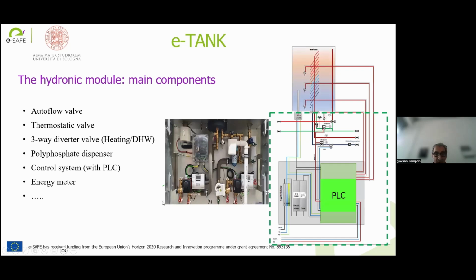The hydronic module's main components are the Autoflow valve and a three-way thermostatic mixing valve for the limitation of temperature for the domestic hot water supply line into the dwelling. Also, a polyphosphate dispenser that limits lime scale formation in the domestic hot water system and in the devices connected to it, and an ultrasonic heat meter to measure the energy consumption. In the control cabinet of the hydraulic unit, electric and electronic cables are installed and wired to all the components. It also includes a PLC.